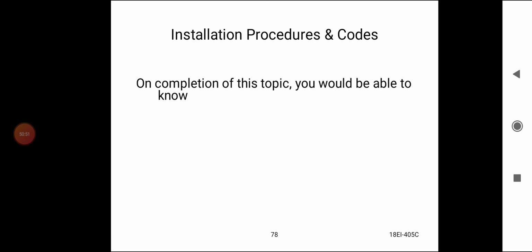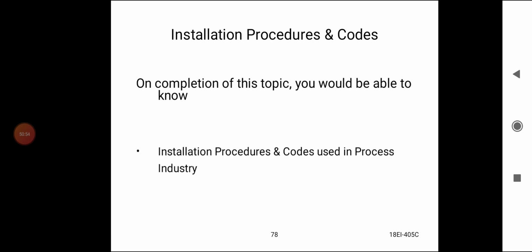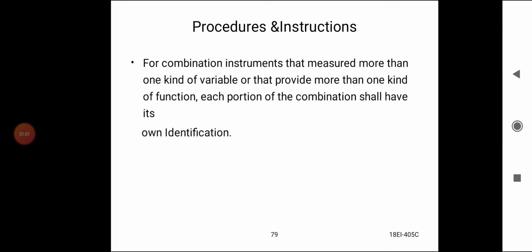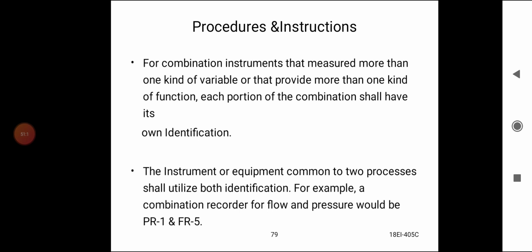Installation procedures and codes. On completion of the topic, you will be able to know installation procedures and codes used in the process industry. Procedures and instructions: for a combination of instruments that measure more than one kind of variable or that provide more than one kind of function, each portion of the combination shall have its own identification. Here the instruments or equipment common to two processes shall utilize both identifications. For example, a combination recorder for flow and pressure would be PR1 and FR5. So pressure recorder 1 and flow recorder 5.